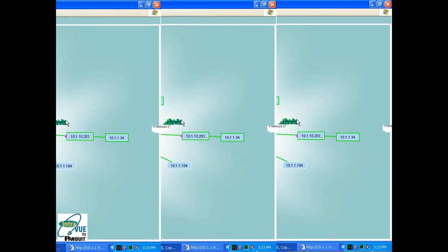Switching to another IntraVUE host, I'd like to briefly show you a few more examples of how our software provides the local technician the information to quickly get to the cause of device problems. In this graph we see frequent failures to respond and disconnections. These are indications of poor connections, grounding problems, or a misbehaving device. The blue spikes, ping failures, in the lower graph are clear indicators of a device having problems. During this time, the bandwidth graph shows the data passing through these ports was not significantly interrupted.